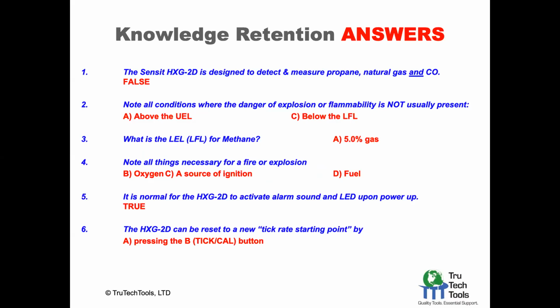The area where the danger is not present is above the UEL, because that's when it's too fuel rich, or below the LFL, the lower flammability limit, because that's not enough fuel for the amount of oxygen present. The LEL for methane is 5% gas. And then the things that are necessary for a fire or explosion are oxygen, the combustion triangle, oxygen, source of ignition, and a fuel.